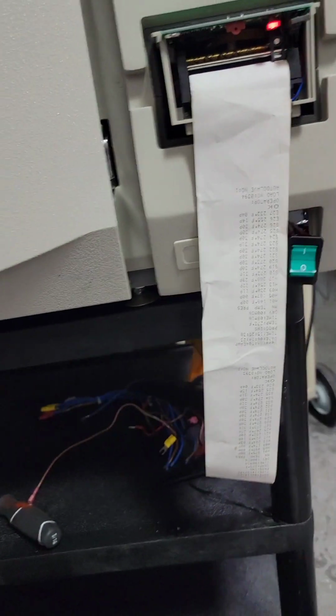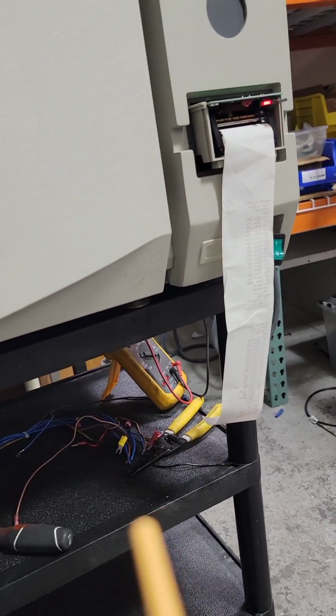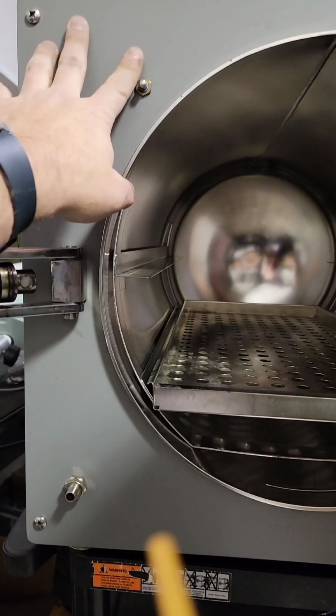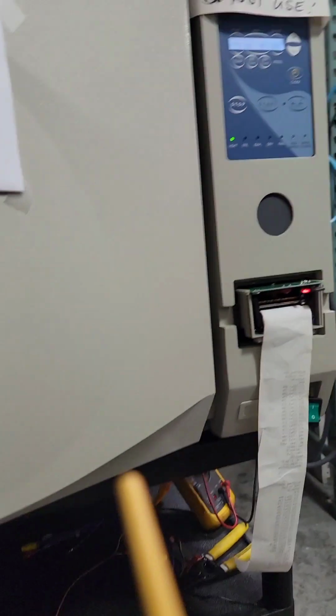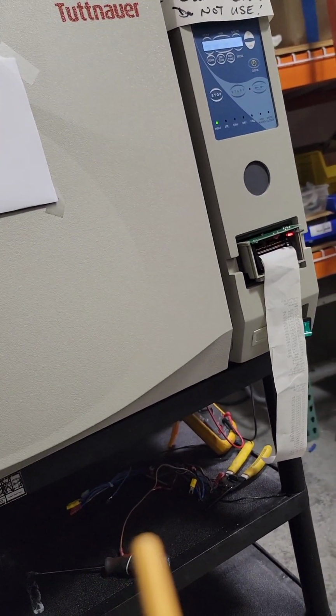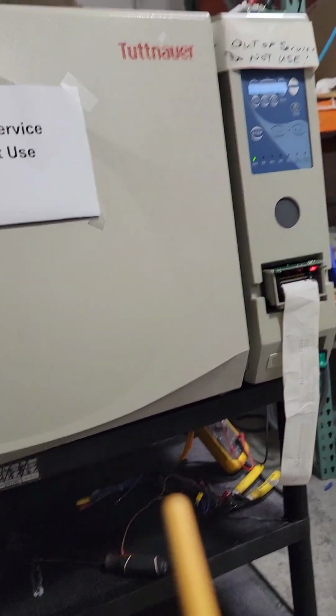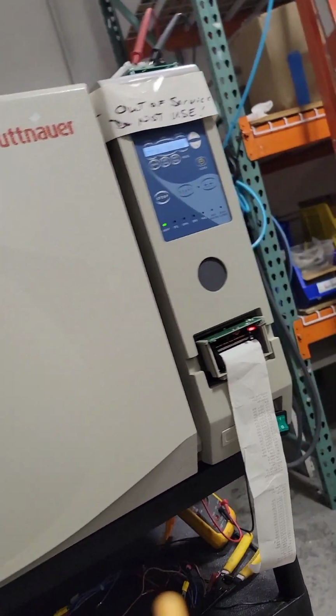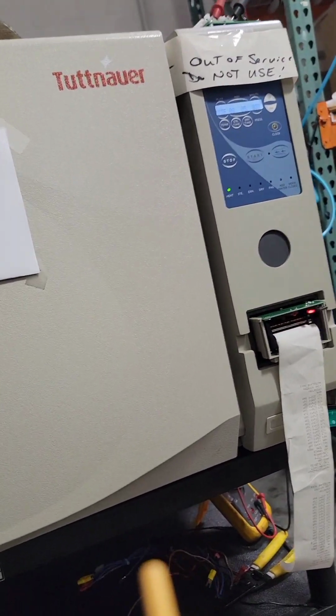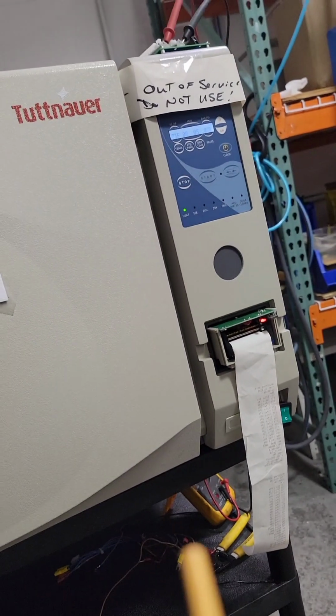If you need to zero it when you turn the unit on, hold the door switch, this guy right here, then give it power. Hold it down for a little bit, and with the door open and you're holding that switch, you should have 0 PSI up here on the front. That's it.